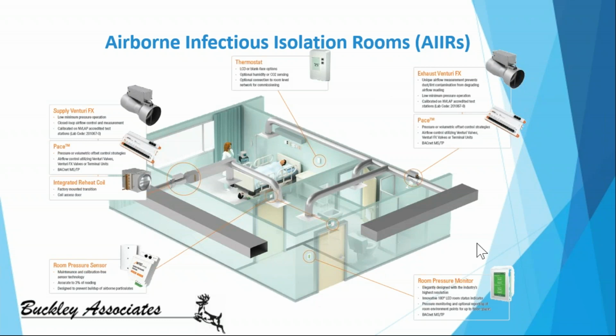So the entire system here is made up of two separate areas. The first room is the ante room or the buffer room. This room remains positively pressurized in relation to both the corridor and the patient room. The patient room, the bathroom included over here, remains negatively pressurized in relation to the ante room or the buffer room. So this ensures that the patient is isolated from the rest of the hospital, as well as the rest of the hospital is isolated from the patient.